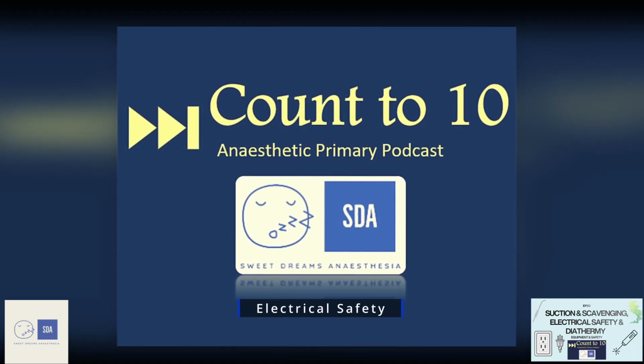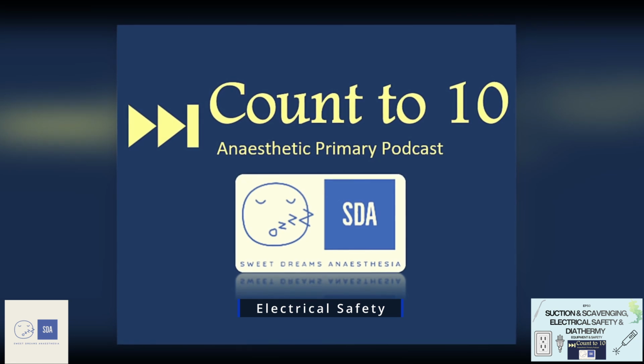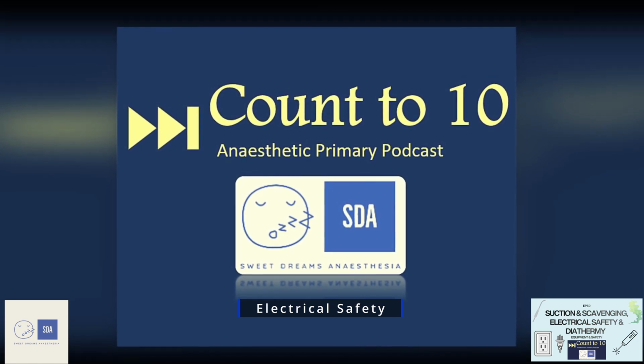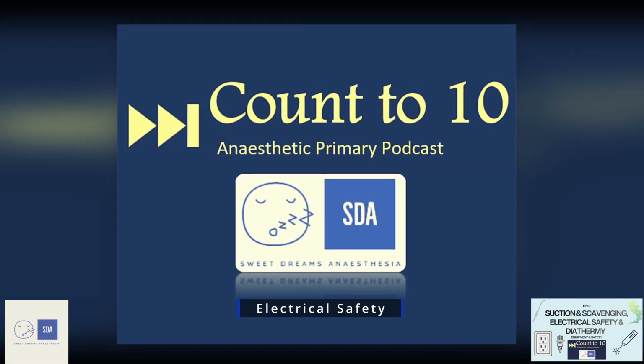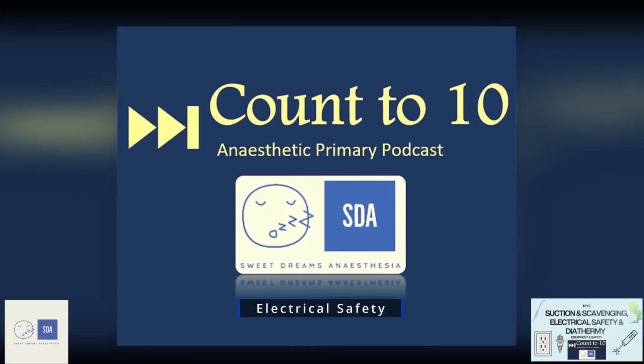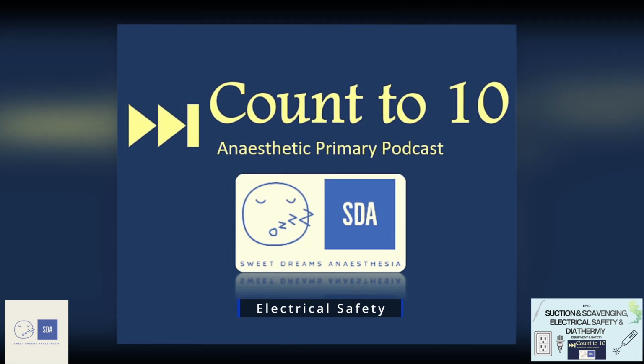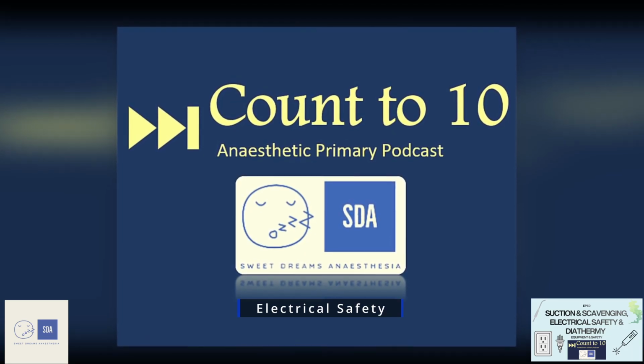But you don't want to have fuses for everything in your operating theatre because you want to be able to run certain things even if there's a small amount of leakage occurring. So what's specific to an operating theatre are certain devices called residual current devices and line isolation monitors.